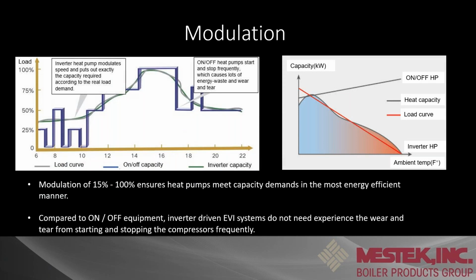On the modulating side, I've been selling heat pumps a long time. I used to work for our Space Pack division, so I've been through the on-off ones, the inverter ones, and the two-stage ones. Based on what I've seen out there, when you have on-off, water volume becomes a huge factor in how this thing is going to operate. Just think of a small loop, primary, secondary. You would absolutely need a buffer tank on an on-off unit, or you'll end up with curves like you're seeing here.